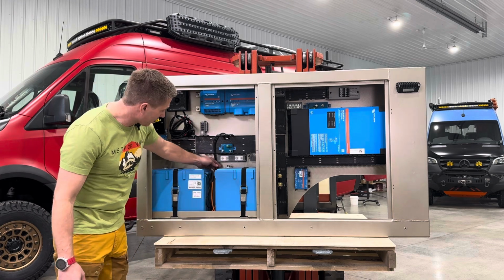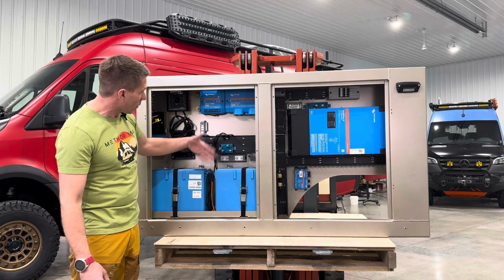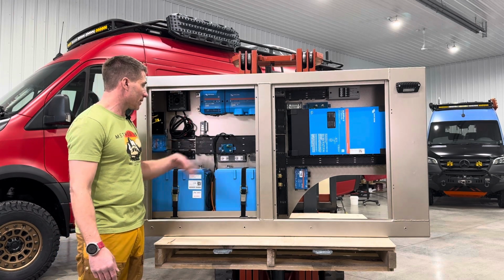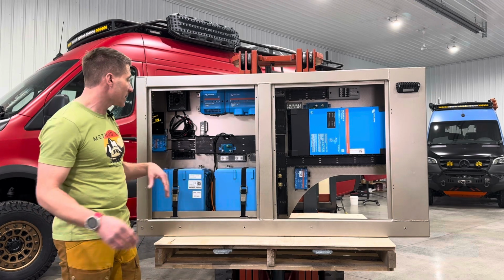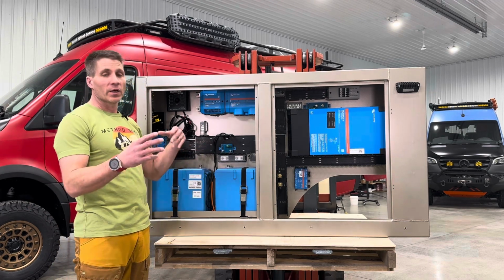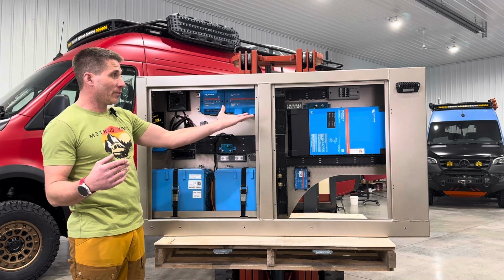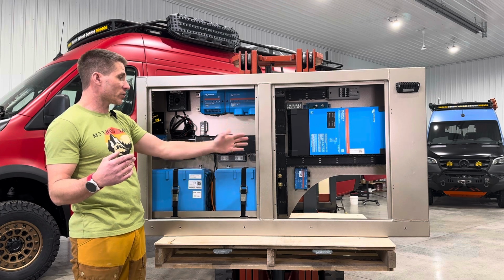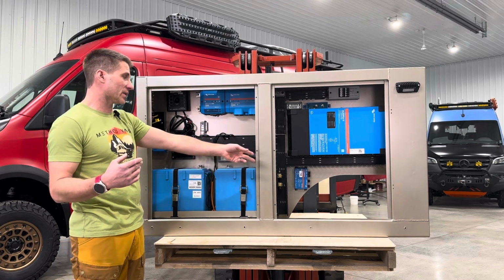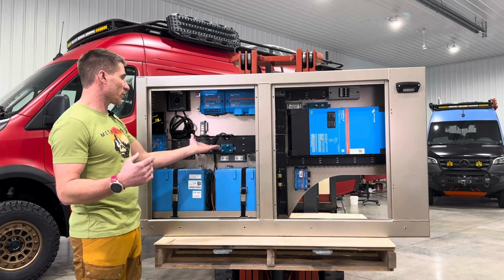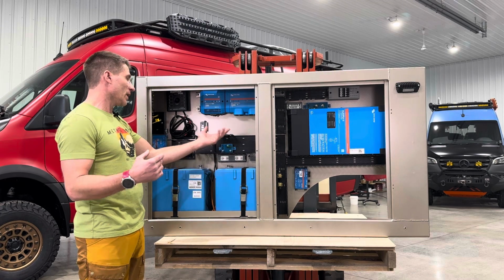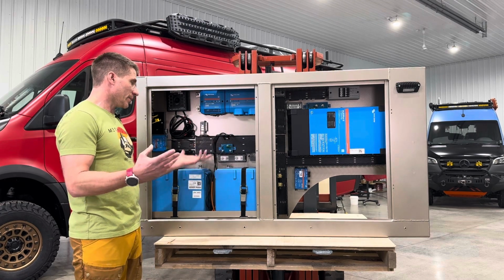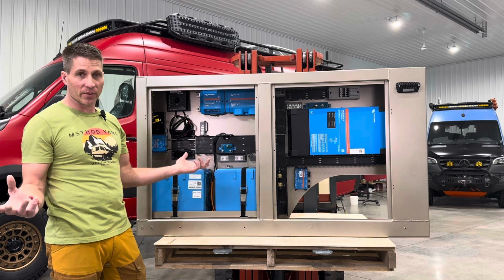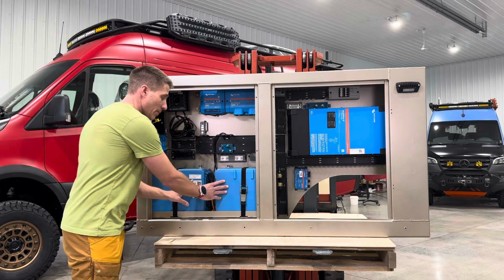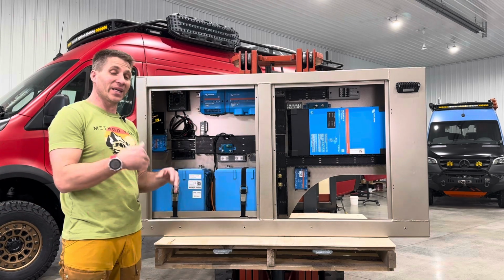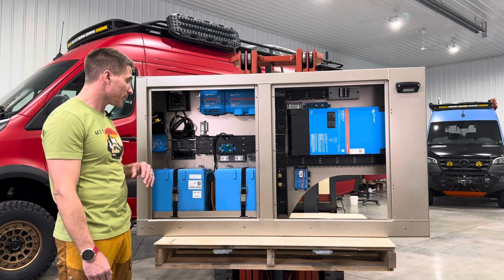These battery heaters, you can see through the cabling here, connect up to this Smart Battery Protect, which gets triggered from the Multiplus or from the Cerbo. In this case, the servo controls a temperature probe, which has a relay that kicks the batteries on to heat when they need to be heating and off when they don't, since they use battery capacity to heat themselves.